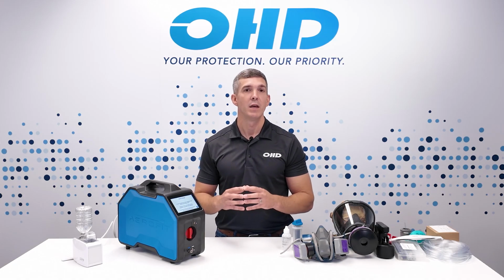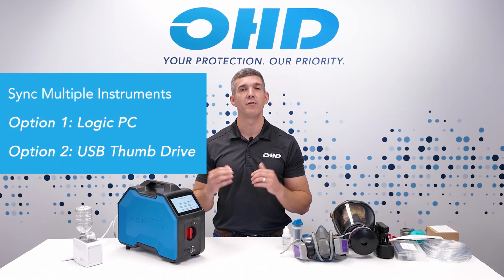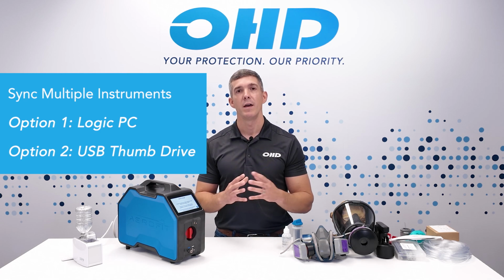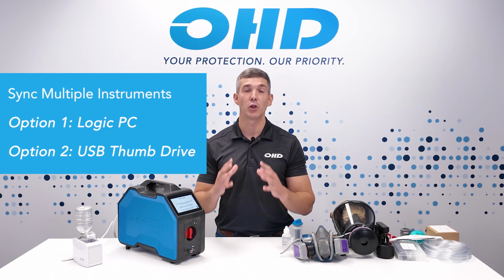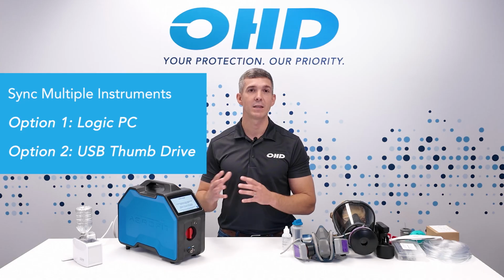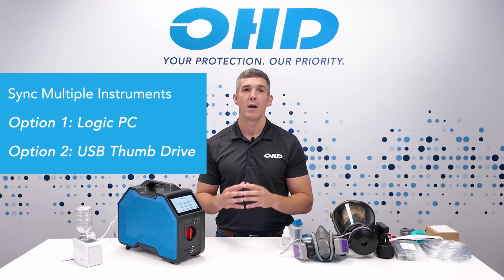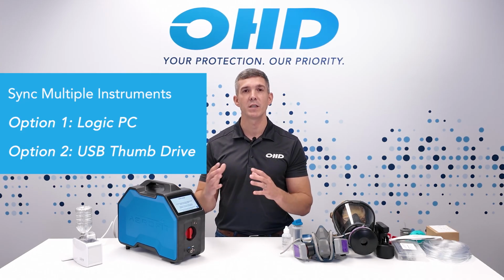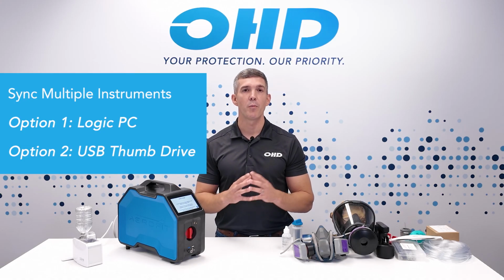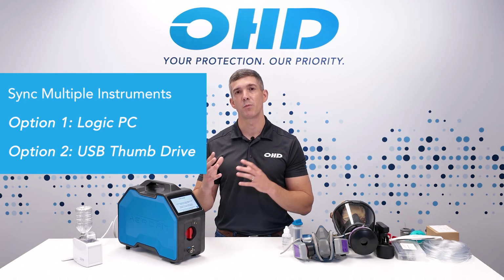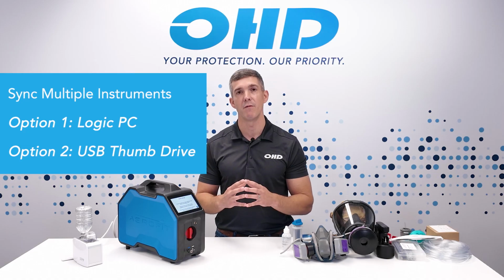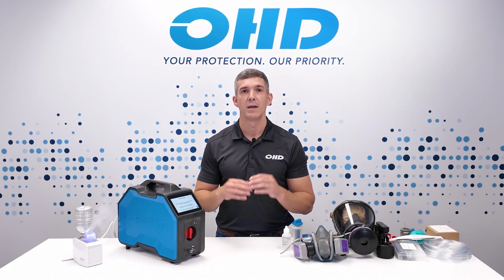If you need to sync multiple instruments, you have two options. Option 1 is to use Logic PC to load your personnel, then sync the personnel to each instrument. Option 2 is to use a USB thumb drive. You can load your personnel to one instrument, then export the database to a USB thumb drive, and then import that database into the other instrument.